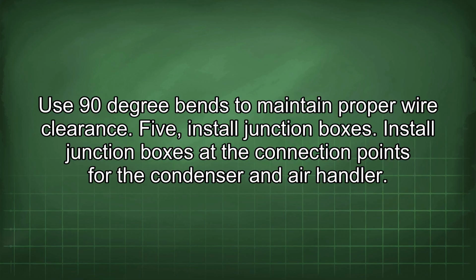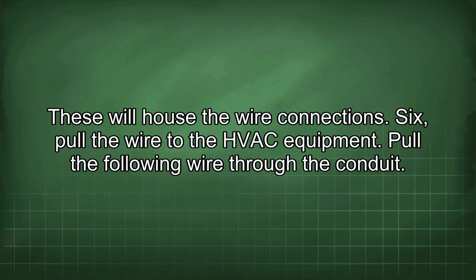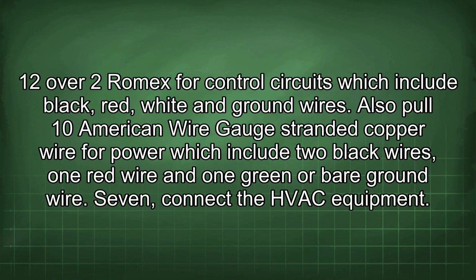5. Install junction boxes. Install junction boxes at the connection points for the condenser and air handler. These will house the wire connections. 6. Pull the wire to the HVAC equipment. Pull the following wire through the conduit. 12/2 Romex for control circuits, which include black, red, white, and ground wires. Also pull 10 American wire gauge stranded copper wire for power, which include 2 black wires, 1 red wire, and 1 green or bare ground wire.